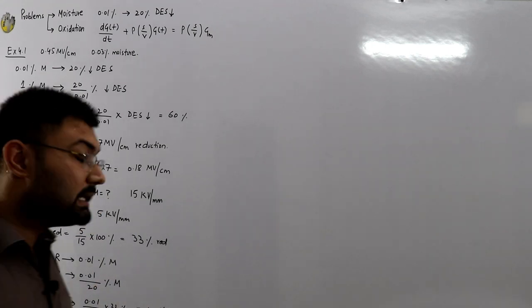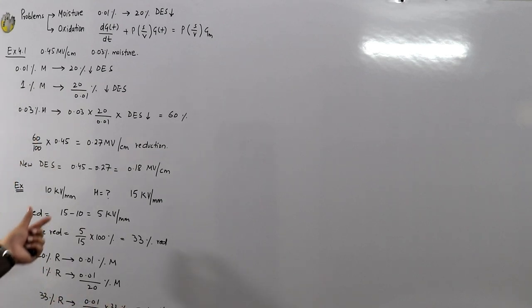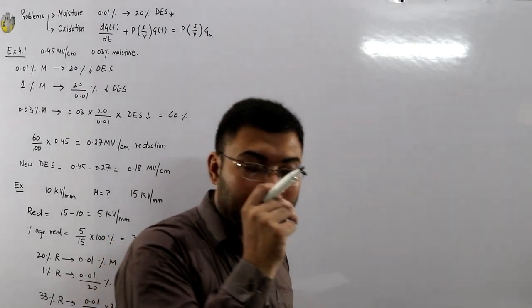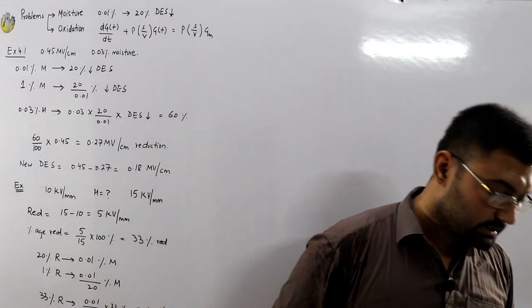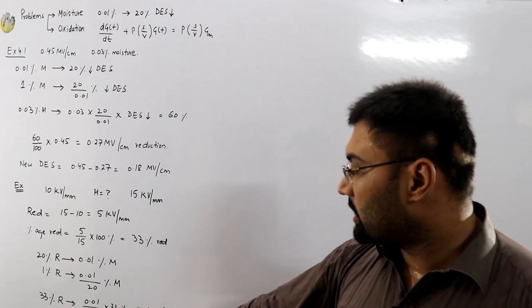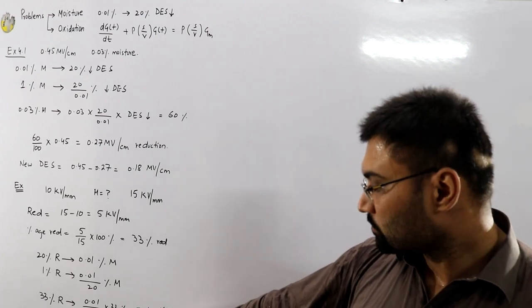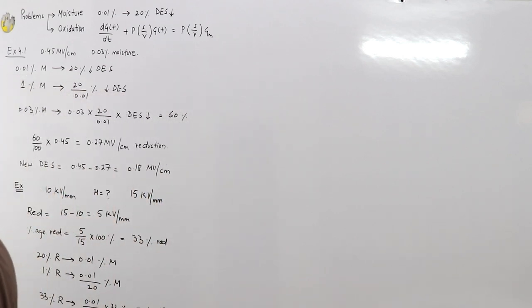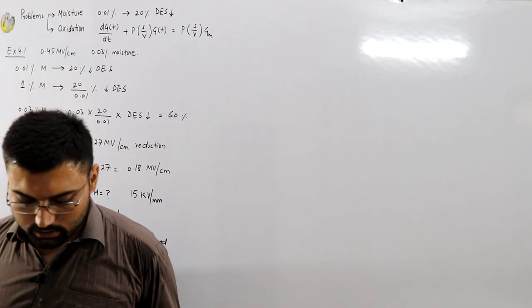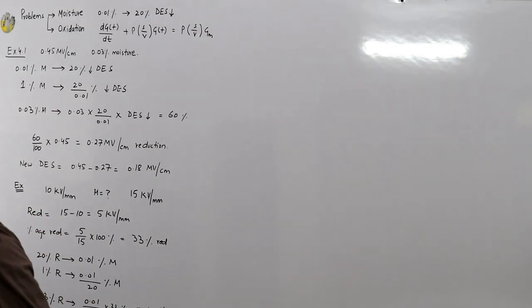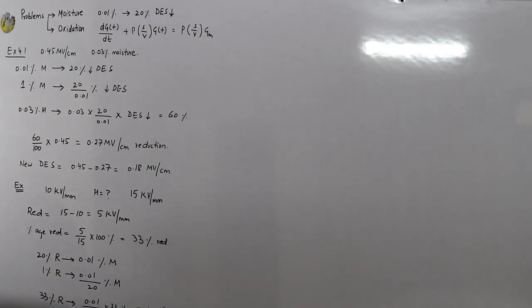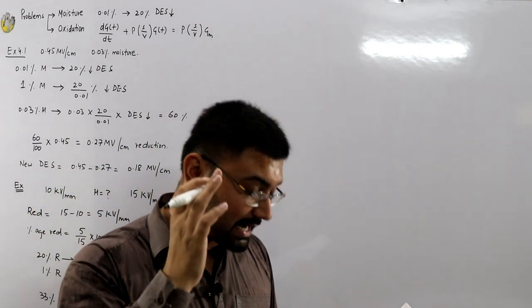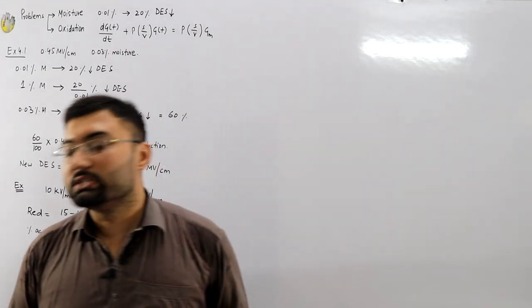10 kilovolt per millimeter is the limit for transformer oil. If the dielectric strength is less than this, you cannot use it. Similarly, if the moisture content is even a point greater than this, you don't have to use it. We've already seen the techniques — when the dielectric strength is reduced, you heat it up to exclude the trapped moisture, then do the filtering.